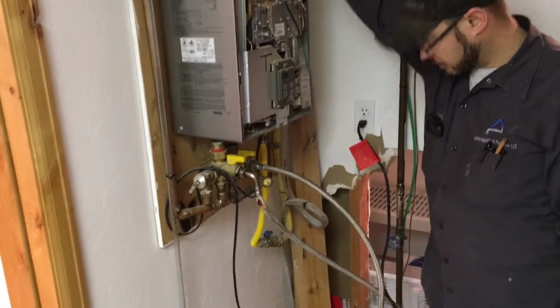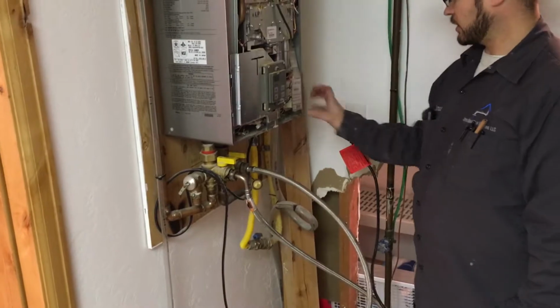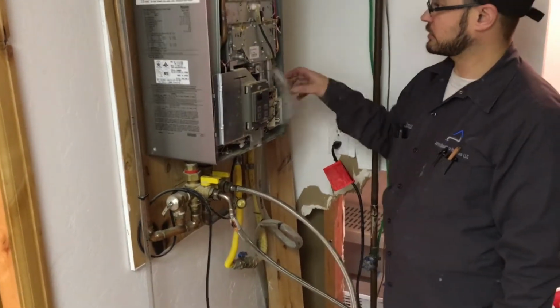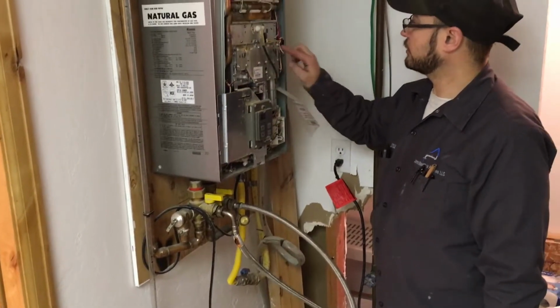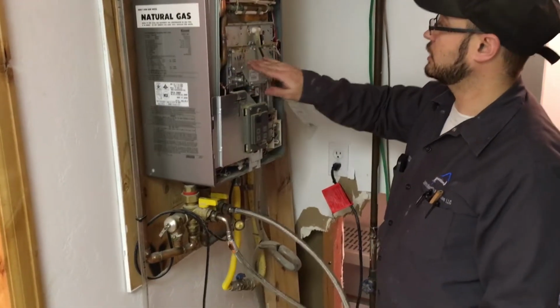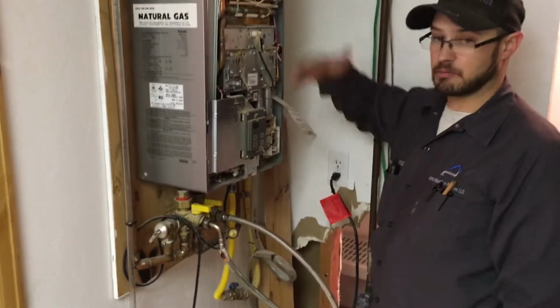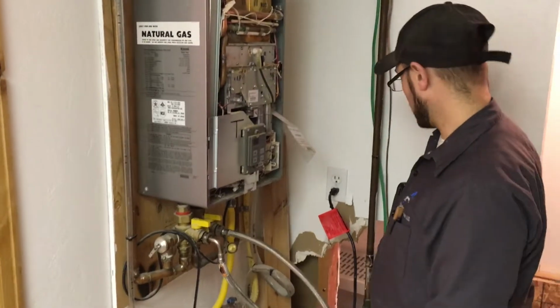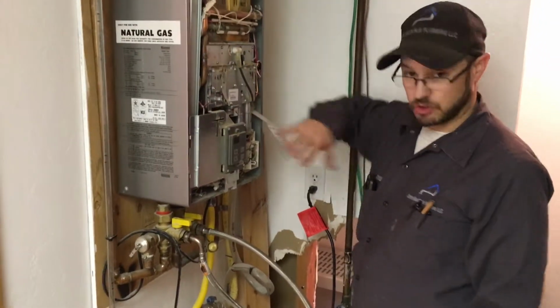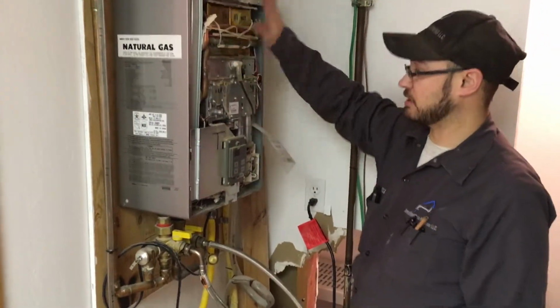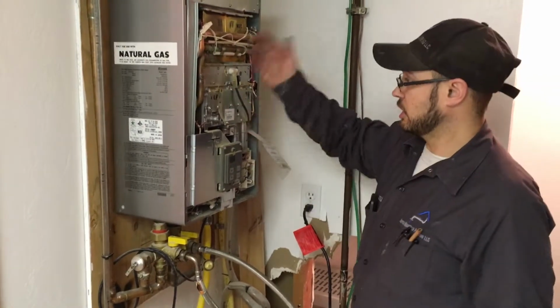We're just going to let that run. While that runs, we take a look at everything, just make sure everything looks good. It looks like there's been some water coming out on here. Now they did have a water leak, so this could have been from condensate building up inside when they had the water leak on this side over here. It got moisture in the air, probably condensated on this, and then when it was running, it probably just charred it.